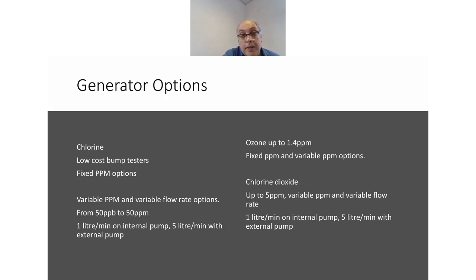Otherwise, we do have more complex generators, as Kurt described, which for chlorine will give you variable ppm and will give you variable flow rate options from parts per billion, 50 parts per billion, up to 50 ppm. The internal pump will generate up to 1 litre per minute, but you can add an external pump and you can generate 5 litres per minute, and it will still hold its calibration and give you the ppm output that you desire.